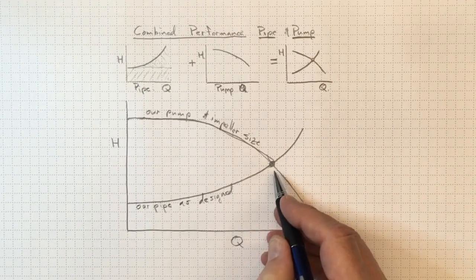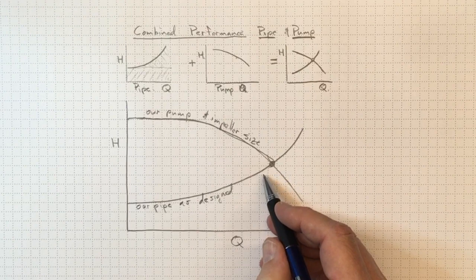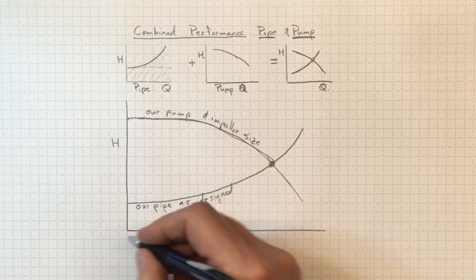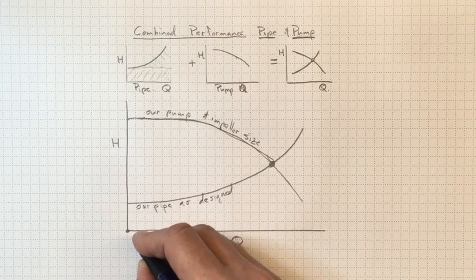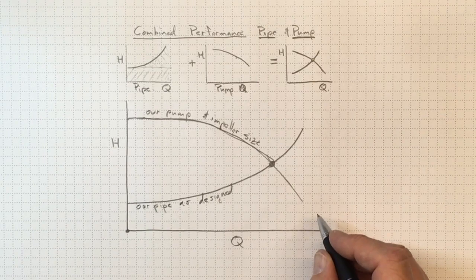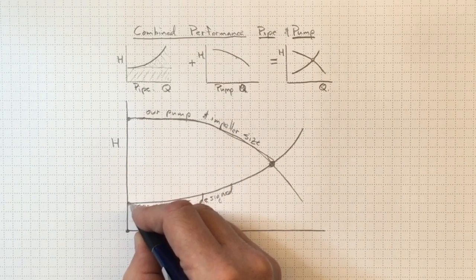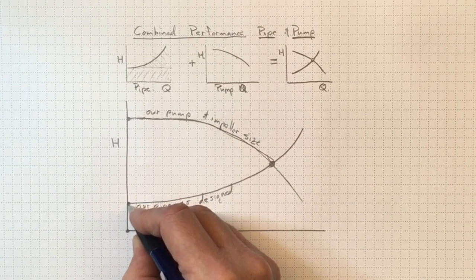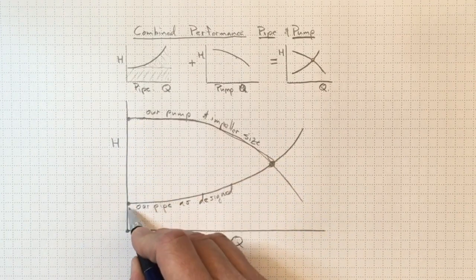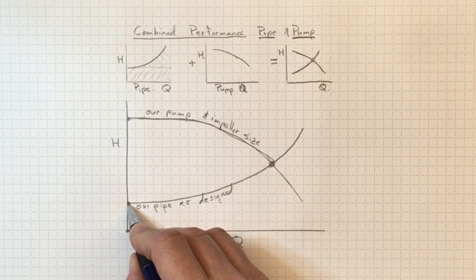Now let's think about this system. It's turned off to start with, and there's a check valve so there's no flow going backwards. So we start off with zero flow and we switch on the pump. The pump spins up to speed and now the pump is producing this much head and there's no flow in the piping system. So that's the back pressure from the elevation.